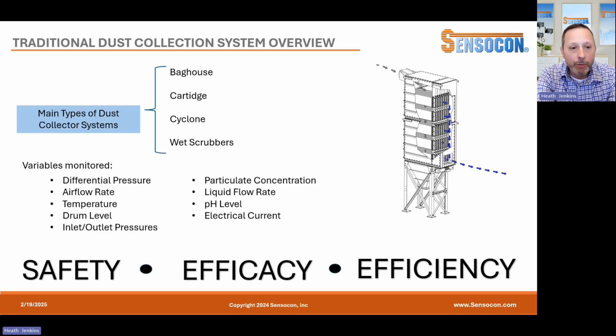There are some standard variables and others that are a bit above and beyond, maybe based on the type of process running in the plant and the type of dust and particulates being filtered out. We have differential pressure, a very common one, done with a gauge, a transmitter, or even a pressure switch. Airflow rate, typically via pitot tubes. Temperature, drum level for indicating when the drum is full and needs to be emptied below the dust collector. Inlet and outlet pressures, particulate concentration, liquid flow rate—particularly in wet scrubbers, to ensure the flow rate matches the gas rate and you get the right amount of liquid entrained into the flowing gas. pH level, which is a bit specialty. And electrical current, which can be used as a predictive maintenance heads up, particularly on the fans.